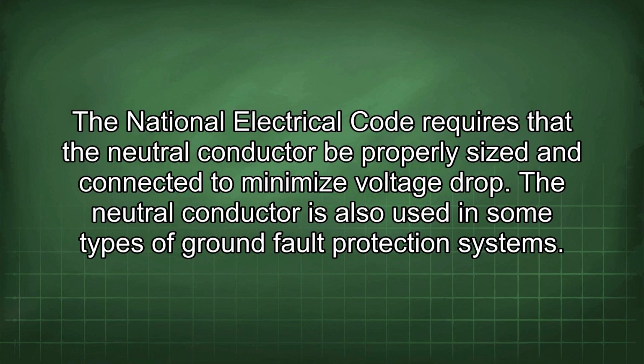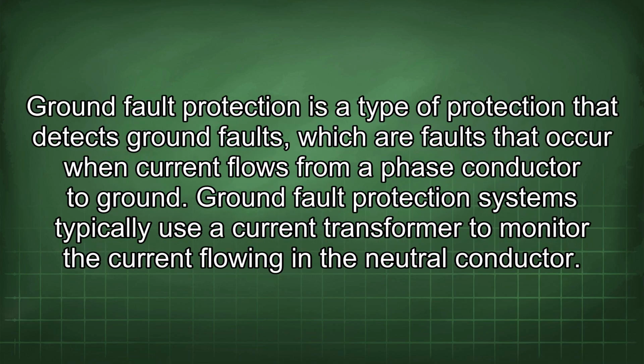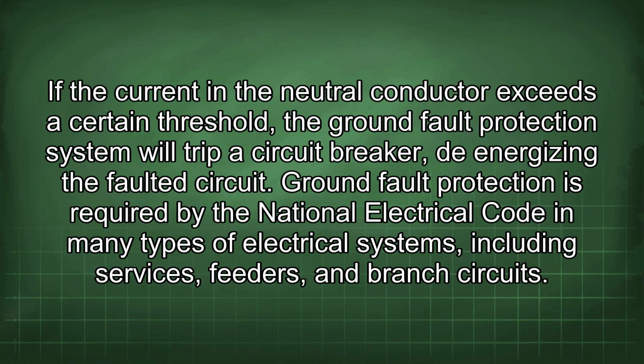The neutral conductor is also used in some types of ground fault protection systems. Ground fault protection is a type of protection that detects ground faults, which are faults that occur when current flows from a phase conductor to ground. Ground fault protection systems typically use a current transformer to monitor the current flowing in the neutral conductor. If the current in the neutral conductor exceeds a certain threshold, the ground fault protection system will trip a circuit breaker, de-energizing the faulted circuit.